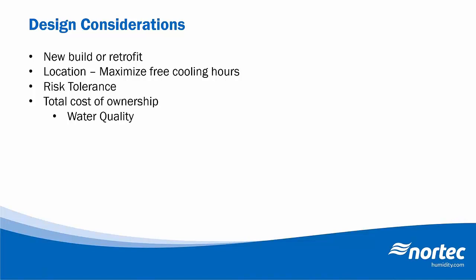And the last design consideration here is the total cost of ownership. So the addition of an adiabatic system, whether it's an evaporative media system, nozzle system, or ultrasonic unit, there's going to be maintenance requirements. So it's definitely something that you need to consider in the total cost of ownership. So media systems will require replacement on the media, typically every 3 to 5 years if it's running on potable water.